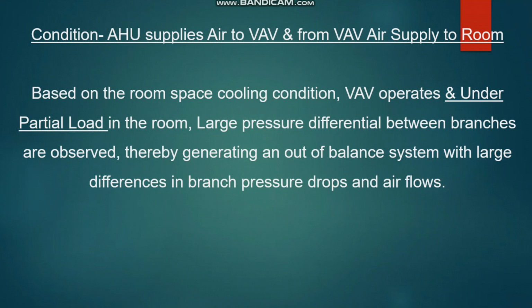Let's start the video. So the first question is, we have a condition where the air handling unit supplies air to the VAV, variable air volume, and from the VAV the air goes to the room. Based on the room space cooling condition, the VAV operates. It may open, close, and adjust, and under partial load in the room, a large pressure differential between branches is observed. Therefore, it generates an out of balance system with a large difference in branch pressure drops and also air flows. So, what will be the reason and how to resolve this?